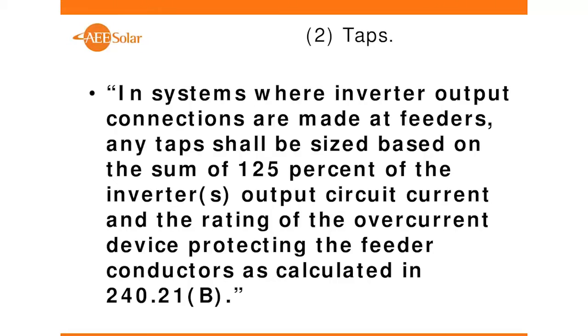Now, what some people have said over the years is that, well, taps screw up everything because you have to worry about the extra source power from the PV, and that's going to add to the utility, and so now your taps are going to have to be sized greater than the size of the feeder. And people have said that. And it's like, what are you talking about? That's just crazy talk. That doesn't understand what taps are. Taps are always smaller than the feeder, and in a tap, we're worried about whether it can handle the fault current that could occur on that tap before it ever makes it to the overcurrent device.